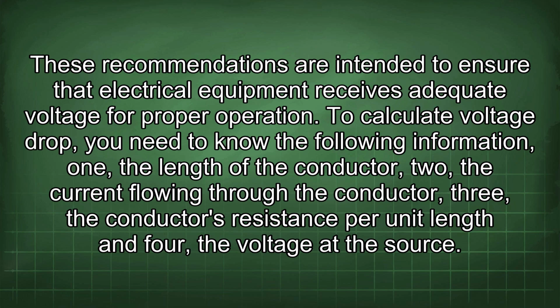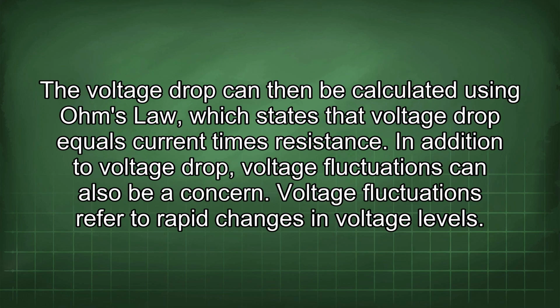To calculate voltage drop, you need to know the following information: 1. The length of the conductor, 2. The current flowing through the conductor, 3. The conductor's resistance per unit length, and 4. The voltage at the source. The voltage drop can then be calculated using Ohm's law, which states that voltage drop equals current times resistance.